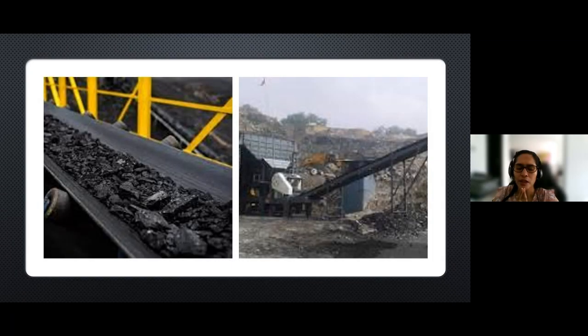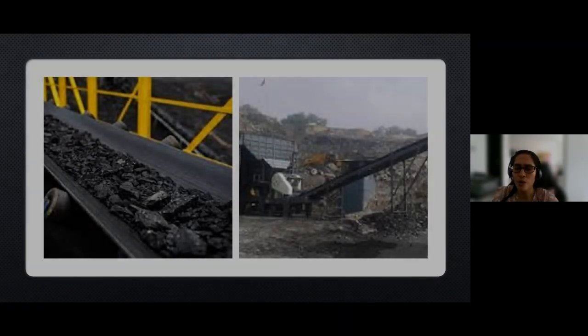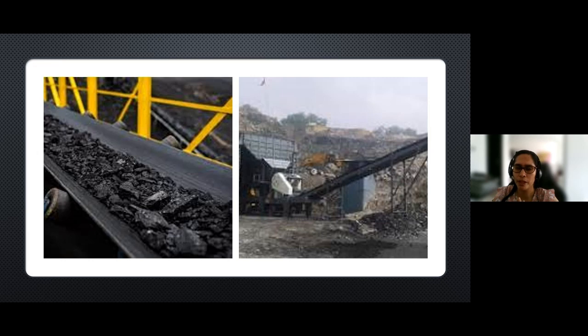Early in my career I learned that the sound of bearings and rollers indicates premature failures, specifically on large conveyor belts. It was so notorious in conveyor belts that move 24 by 7, every day of the week, that they sometimes have repetitive sounds from the bearings and rollers. These sounds are a good indication of malfunction. Something we realized is that the power consumption of those conveyor belts was also impacted. So it is important to understand the situation and try to establish the baseline.